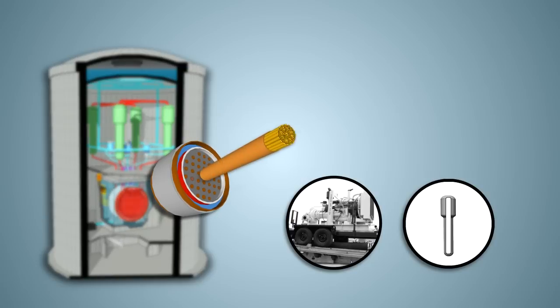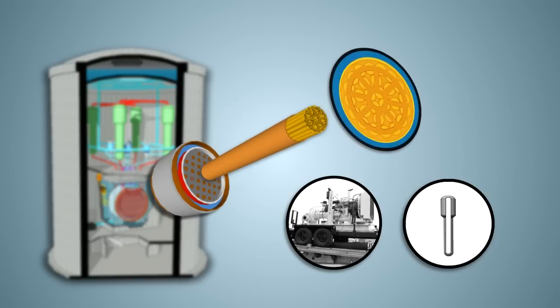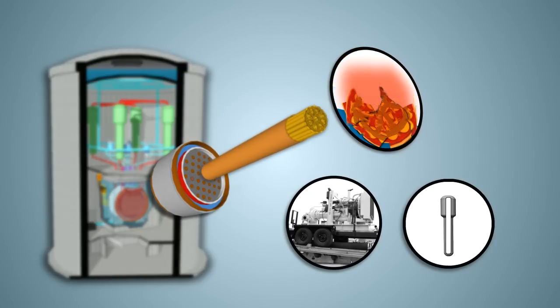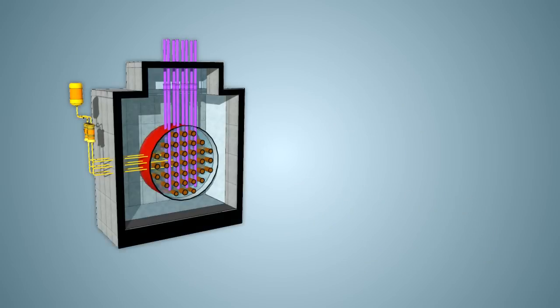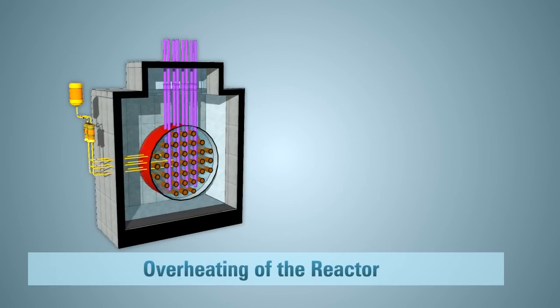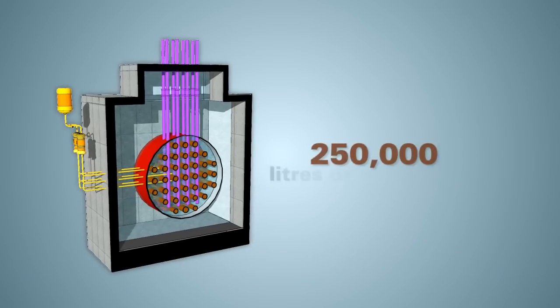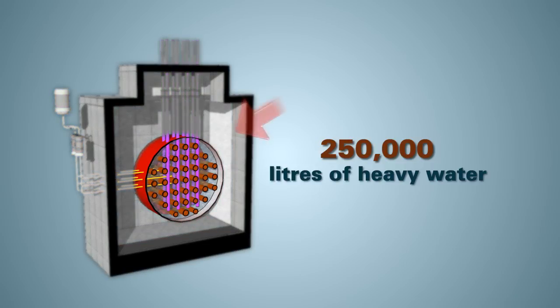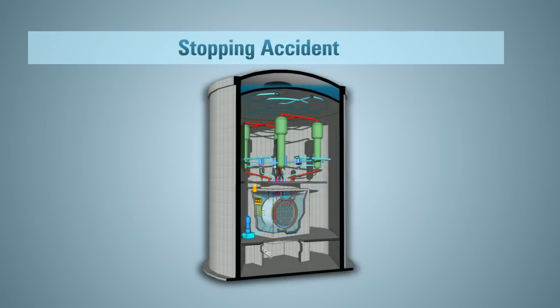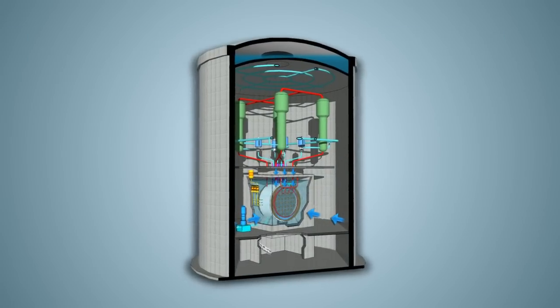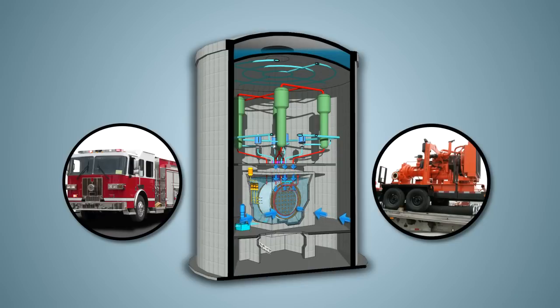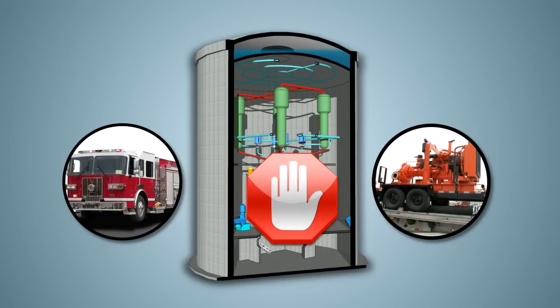Once the water in that system boils away, there is limited fuel damage. If nothing is done at this point, the 250,000 litres of heavy water inside the Calandria starts to heat up. The Calandria is what holds the fuel. Supplying water to the Calandria using emergency equipment such as fire trucks would stop the accident.